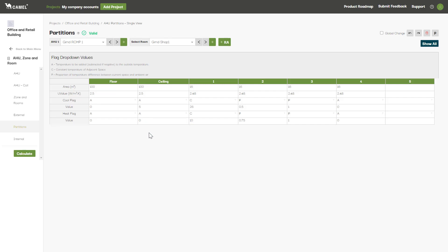The third and final option is the P flag, which sets the temperature for the adjacent space to be at a proportion of the temperature difference between the room condition and the ambient condition. Entering 0.5 here means the adjacent space is halfway between the room temperature and the ambient temperature. P1 is the same as the ambient temperature, so 0.75 here means the adjacent space is three quarters of the way towards the ambient temperature from the room temperature.